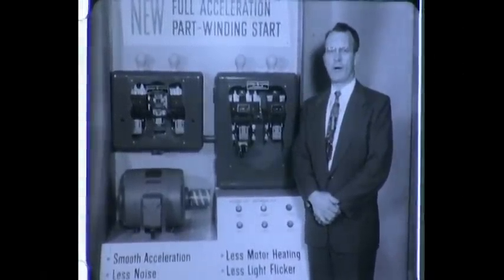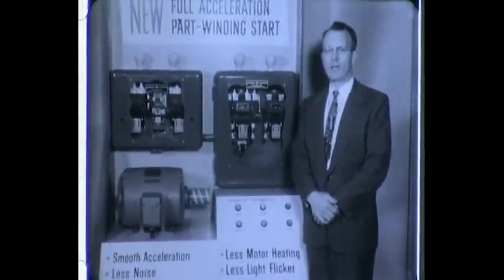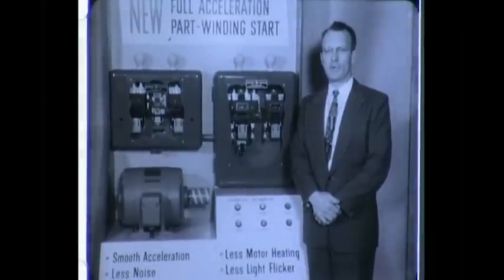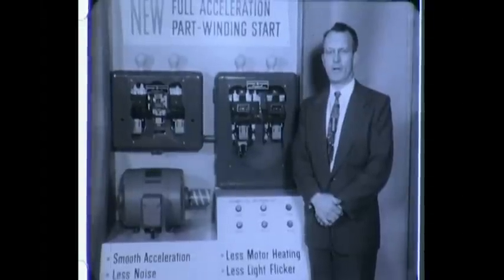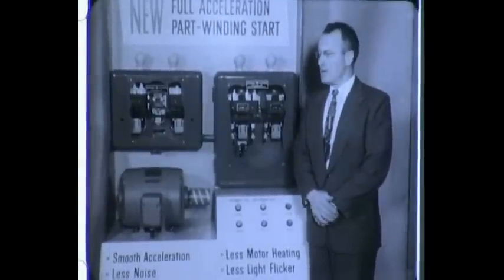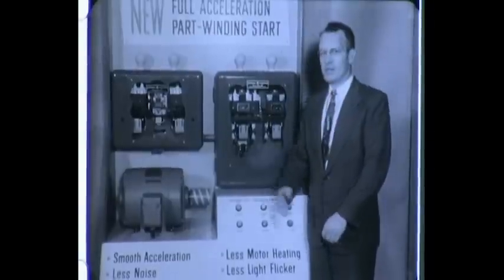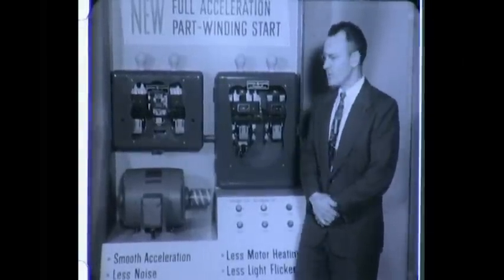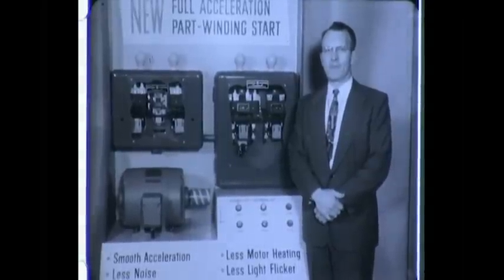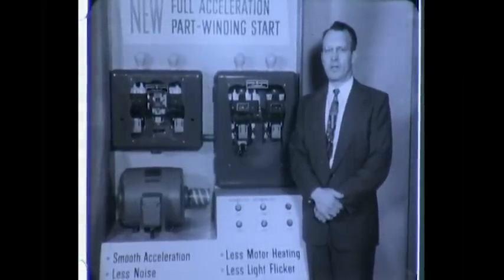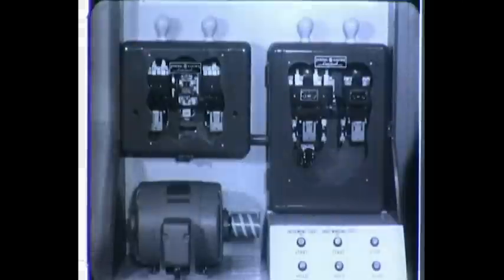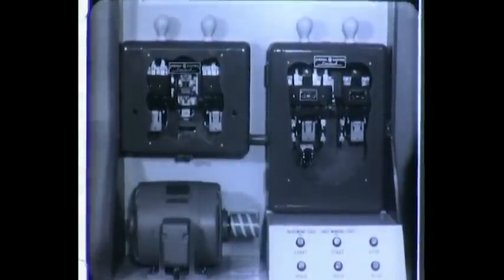This part winding package can be used economically where power companies limit inrush current on systems from which both power and lighting loads may be drawn at the same time. The CR7050 starter is designed for use with the standard stock motor. This combination of motor and control limits inrush current, thereby reducing light flicker. For comparison, let's see how the conventional part winding starting method works.